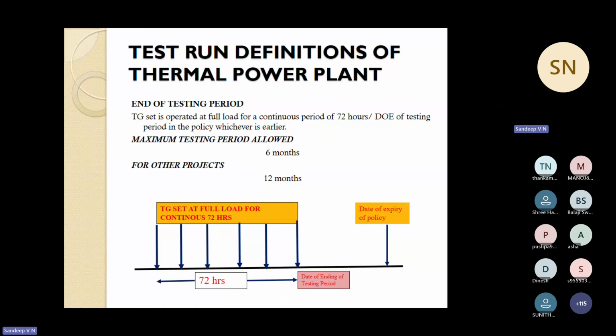So as I told you, the erection premium is considerably less. So normally the principal will try to extend this testing period. He will run the plant at 100 megawatt for 70 hours, then reduce the load to 90 megawatt. So it will go back again to the normal stage. Then again gradually the load will be increased. When it becomes 71 hours, again the load will be reduced. Once it reaches full load and operates continuously for 72 hours, at that moment it will be declared as the date of commercial production.